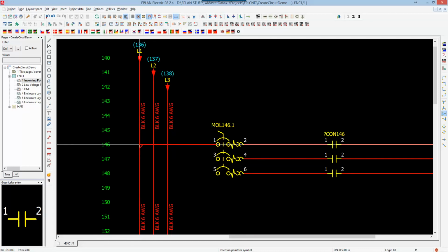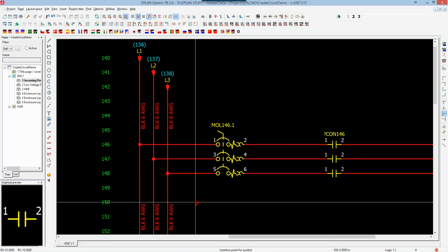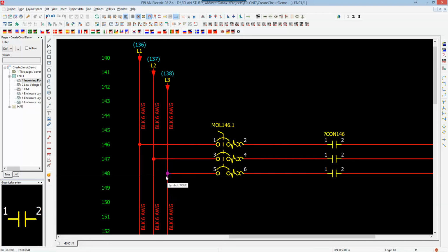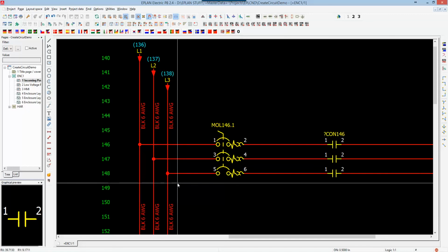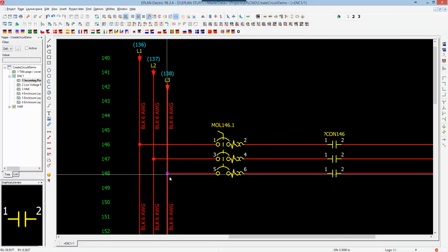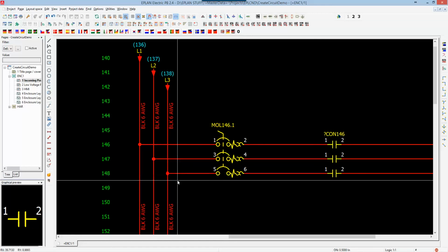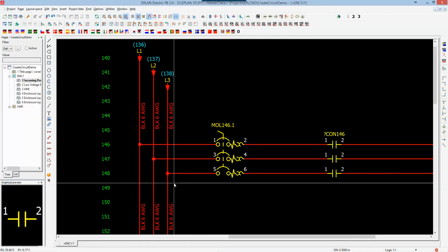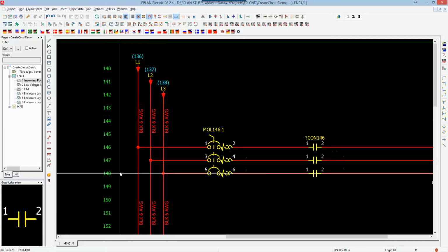And all I have to do is position myself where that first connection is going to meet, where they're going to cross, and I can also hold my mouse button, drag a line diagonally, and all three are going to automatically connect. As soon as I let go, those are now connected, and those show me here a little dot to represent that those are junctioned right over there. Now, of course, if you want to use the dot, you can use that representation, but you can always change that representation to look like the default IEC type representations if needed. Those will be in the project settings.